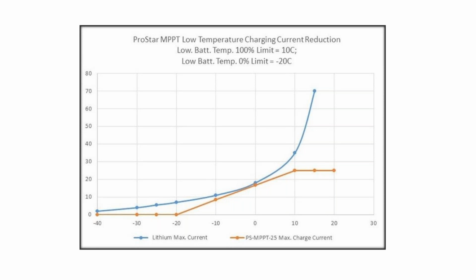Here's the example I mentioned earlier in the ProStar MPPT. When we enable low temperature current reduction, we program in the low voltage, the low temperature range and the higher temperature range, and across that point you can see in orange the current will be reduced. The battery does not want to see an amperage greater than what's in that blue graph, and the orange graph shows the ProStar keeping the current level below and linearly derating so it's always kept beneath the max current rate the battery wants at a given temperature. You don't want those lines to cross, and the ProStar prevents that with this programmability.